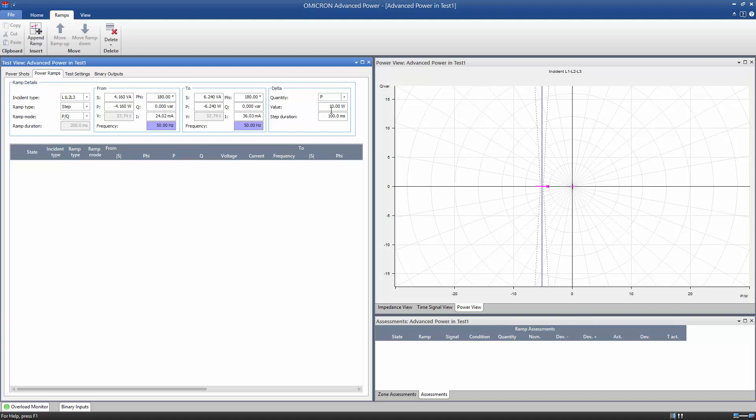Delta can be entered as a pure power P with a value of 1% of the expected pickup value and the step duration should be longer than the inherent operating time of the relay.